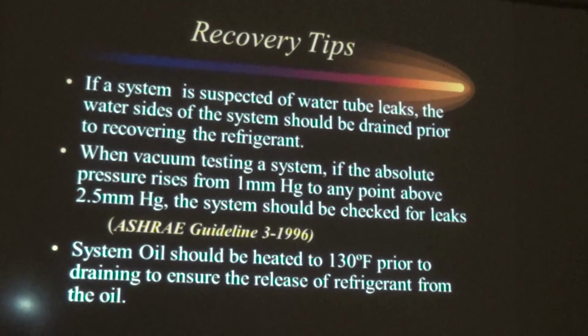Recovery tips. If a system is suspected of water tube leaks, the water sides of the system should be drained prior to recovering the refrigerant. When vacuum testing a system, if the absolute pressure rises from 1 millimeter mercury to any point above 2.5 millimeters mercury, the system should be checked for leaks.